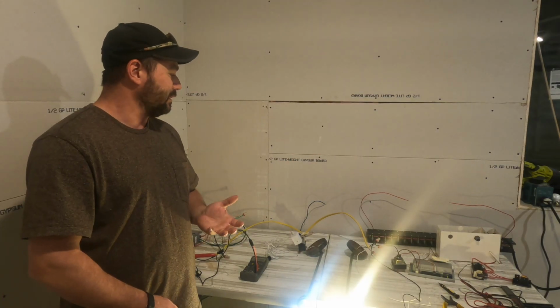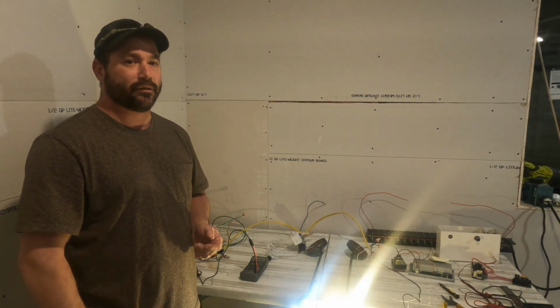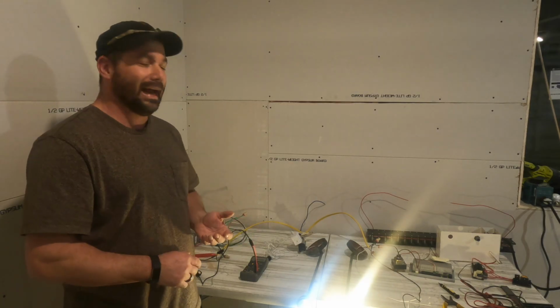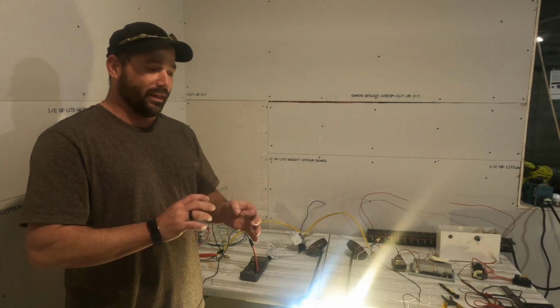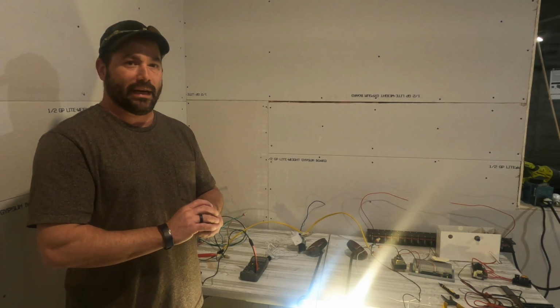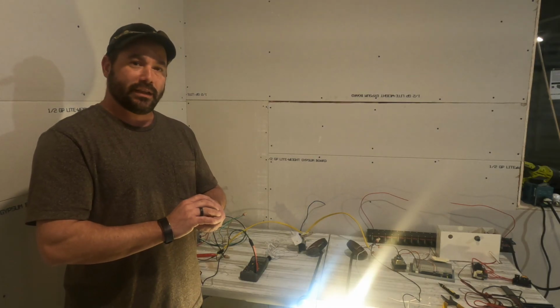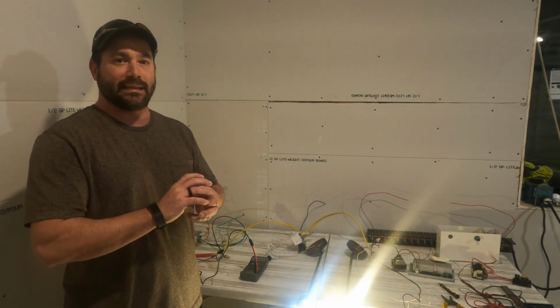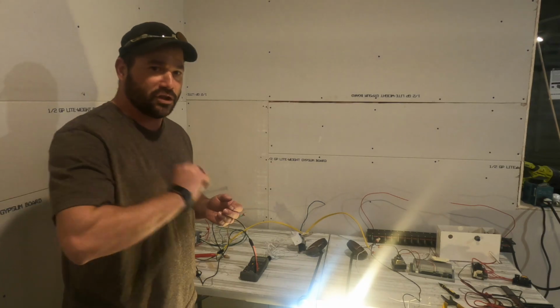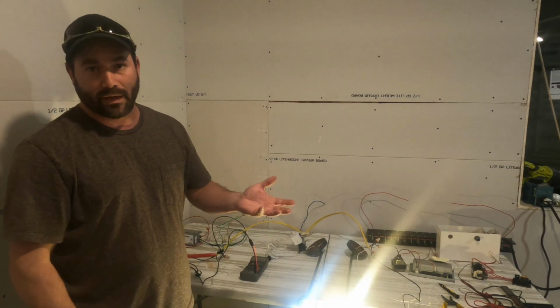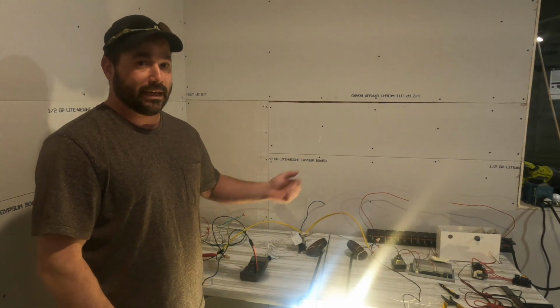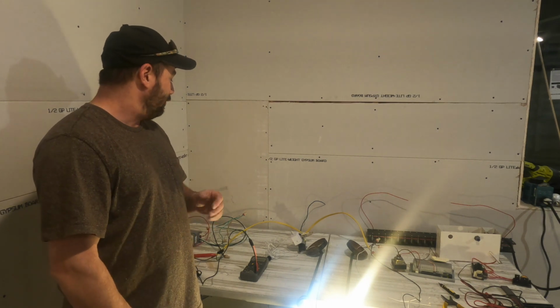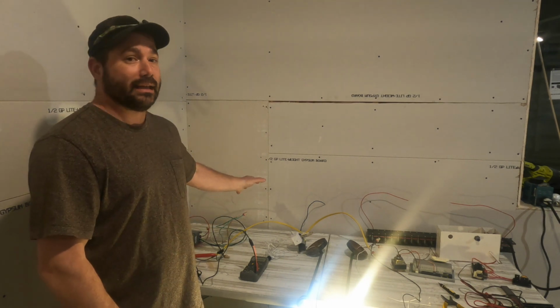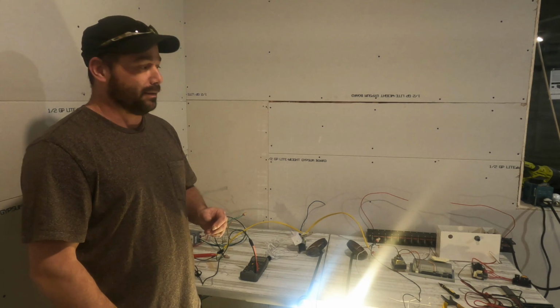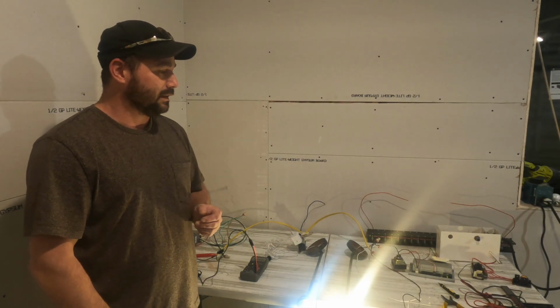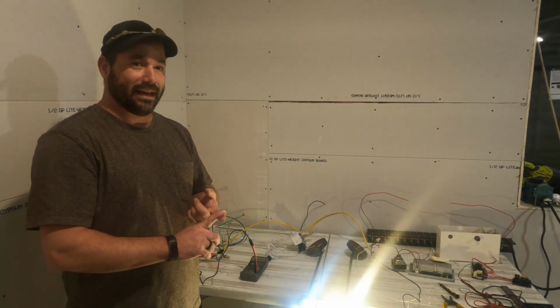I'm not having it ground or shunt to ground in any part of my house. And I suspect that they're using MOVs, which are metal oxide varistors, to shunt to ground. And how those operate is you've got a disc with a dielectric breakdown in it. When it hits a certain voltage, it goes from infinite resistance to zero resistance, which would shunt directly to ground or whatever the other probe is hooked to, which in this case is more than likely ground. I have a feeling that if you had a floating ground, this thing would not operate properly and potentially kill electronics. So keep that in mind too. You have to have your ground connected.